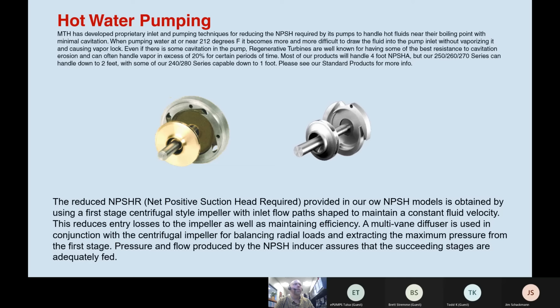But when you get into a situation where you've got a large facility and you have a large pump, one of our multi-stage regen turbine pumps, and you're going to be running the higher temperature water, and you need even lower NPSH, using an inducer, which is actually a centrifugal impeller in front of those regen turbine impellers, will lower that NPSH even further, to where it's as low as even 2 feet. Some of them even as low as 1 foot. So we can hit very low NPSH with our pumps, and that's one of our big advantages.